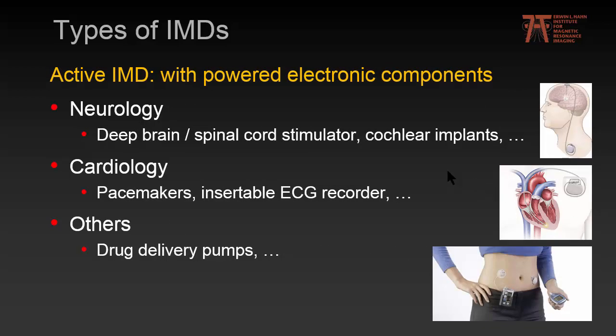Active IMDs come with powered electronic components. Examples in neurology are deep brain or spinal cord stimulators and cochlear implants. In cardiology, we have pacemakers and insertable ECG or loop recorders, and others may be drug delivery pumps. The electronics are housed in the CAN, or IPG — implantable pulse generator — which is connected to a wire called the lead.